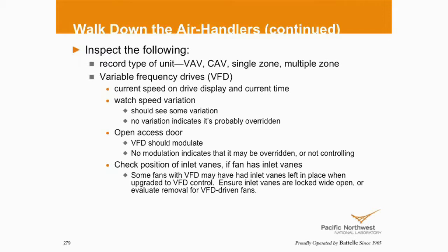Is it a single zone, constant volume? Is it multiple zone? Is it VAV? Does it have VFDs? Does the VFD tell me how fast it's running, how much load, amperage-wise? If I open the door, either on the return or discharge side, do I see the static pressure change and therefore the fan respond to that? If not, it probably means it's overridden.